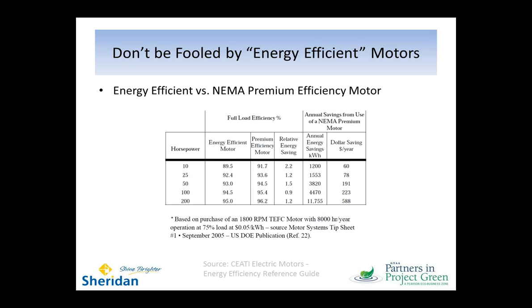Just another quick note: watch out for the labels. It's still possible to find a motor that's billed as green or energy efficient, but actually really doesn't live up to the label. So you can see here that there's a motor described as energy efficient. Its efficiencies are in column 2 for 10 horsepower through 200 horsepower. And compare it to a real NEMA premium efficiency motor. You can see that there's a variation of 1 to 2% difference in efficiency, and it would make quite a difference in your dollar savings.